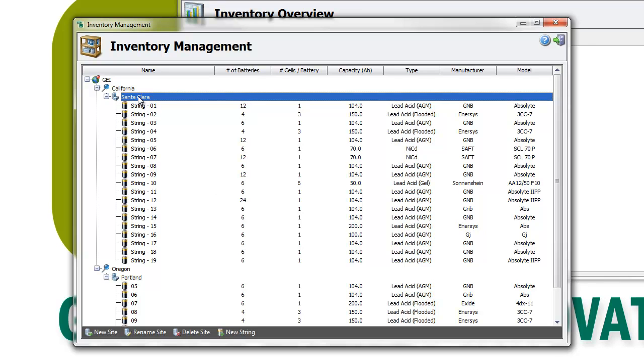IBMS will indicate when the item to be deleted is still associated with test results with an error message. In this case, you must erase all test results associated with the string before erasing the string configurations.